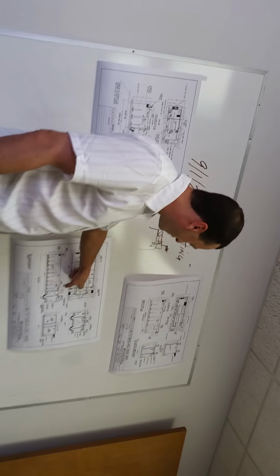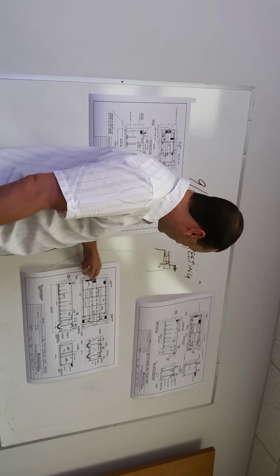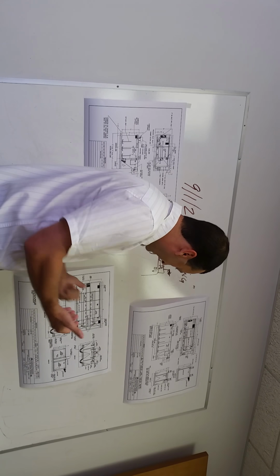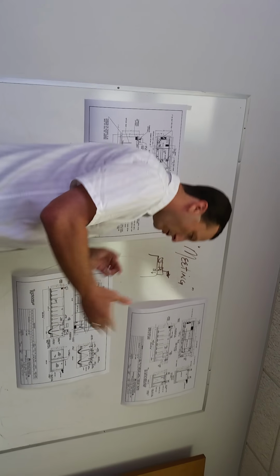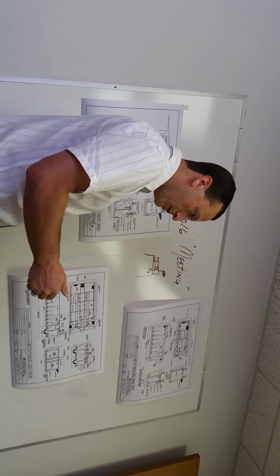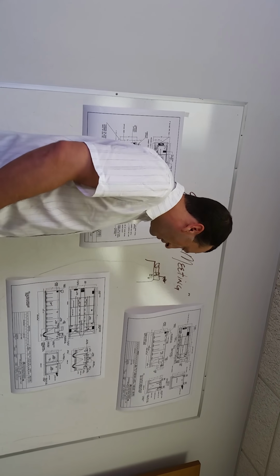When it all gets to the field, they'll set it all down and pull it together. They're going to have to do a continuous weld on the inner portion of the bottom, and then on the end walls, they're going to have to do inside and out welds. We don't worry about the underside of this.